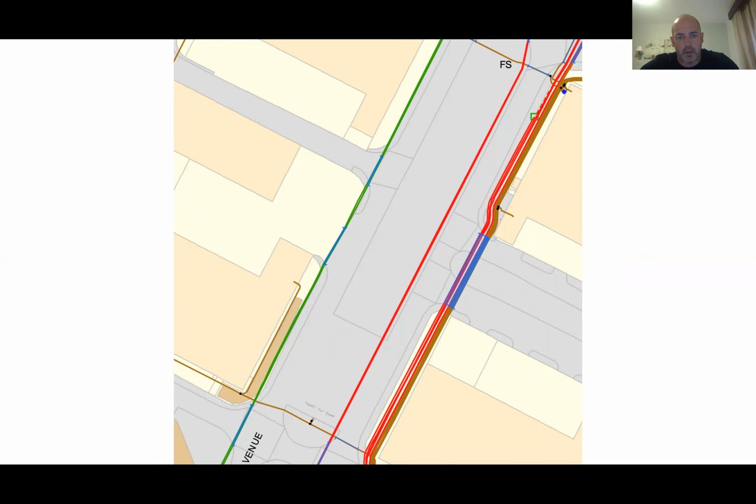Another Scottish Power drawing, this one is showing a 33 kV cable up here, and we've got high voltage here, 11 kV, and then we've got LV across here. So one thing to spot on here is if we saw any columns here, we should know that we can't feed columns off high voltage. So again, the same thing applies. They're not going to be fed off this cable. Where do they get the power from? And let's have a look at that street.